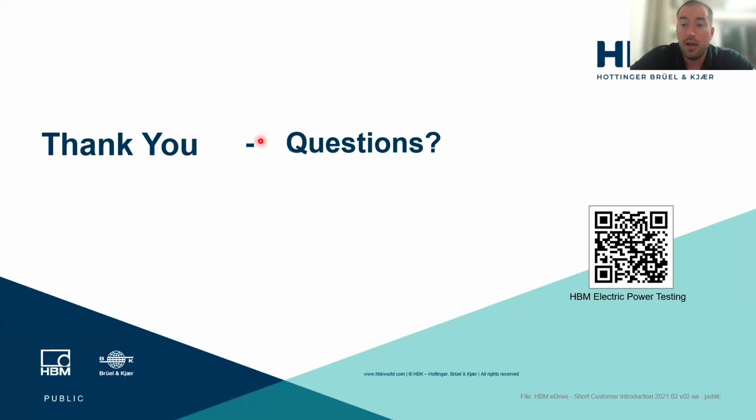Mike again. Does cable shielding actually help? Some of our recent tests suggest it causes more problem than it fixes sometimes. Certainly, but this is probably coming back to your shielding, or excuse me, your grounding path. So if you're having issues where shielding is not helping things, really sit down and look at the path to ground of everything, because you likely have some sort of loop going on.